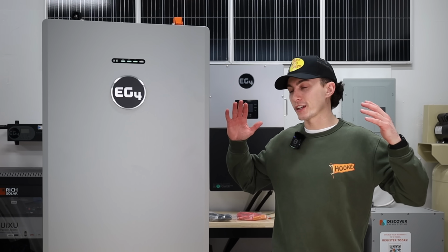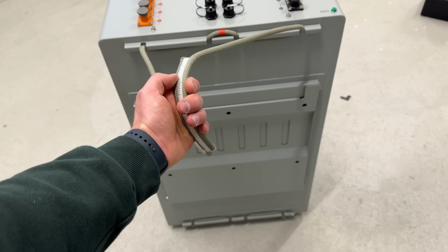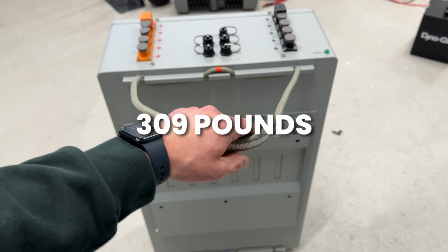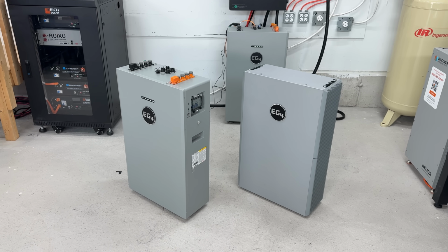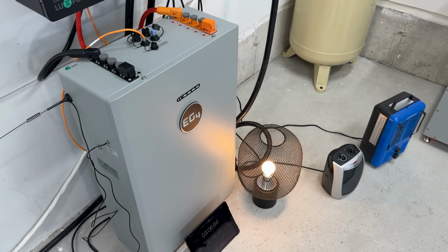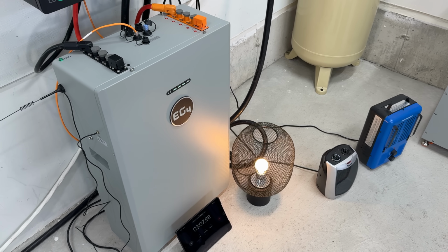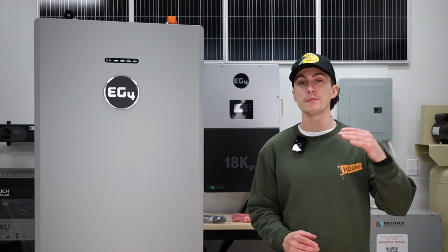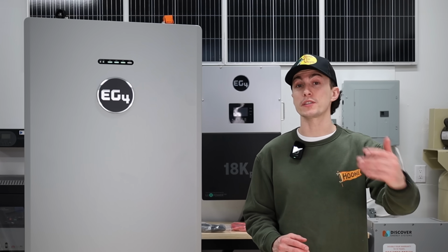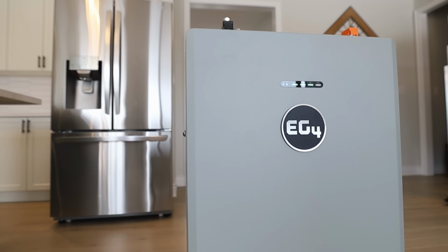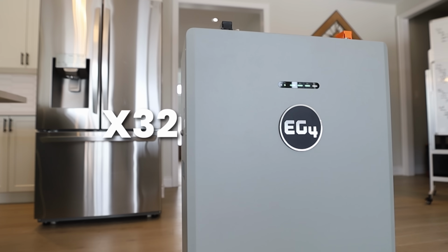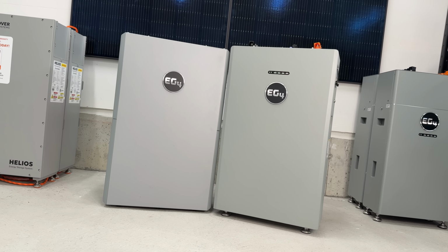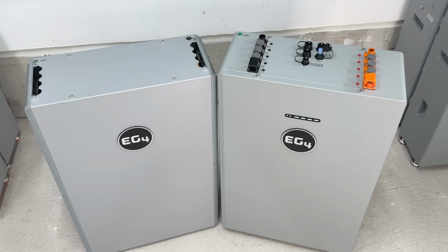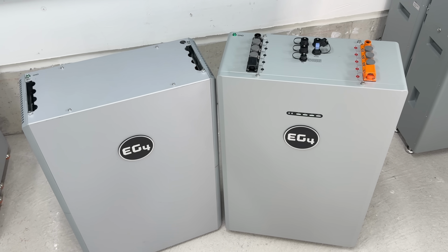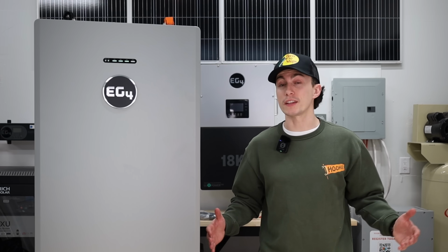First up, this thing fails the tiny baby lift test. It weighs in at 309 pounds, which is 15 pounds more than the indoor version. These bigger batteries have 314 amp hours or 16 kilowatt hours of storage, but they maintain the same 200 amps of continuous output. These batteries are 48 volts, and you can pair up to 32 of them together as long as you're pairing Gen 3 BMS with Gen 3 BMS, which means you can get a total of up to 512 kilowatt hours of storage, which is enough to power Manhattan. Not really, but maybe Manhattan's basement.